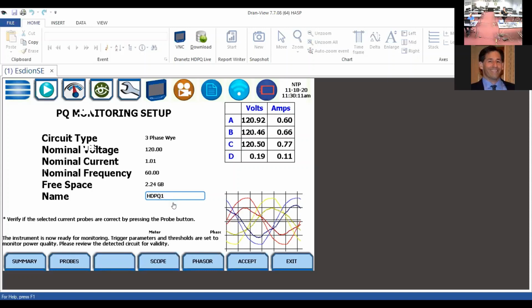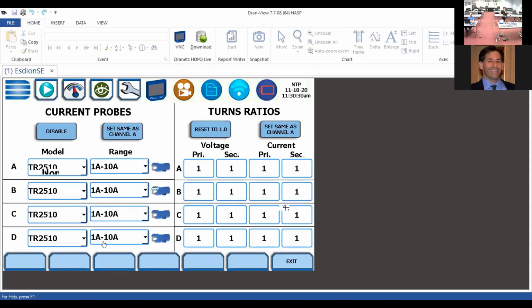The second place in which you would enter information to complete your monitoring setup is the current probes. The instrument wants to know what current probes you are using. By clicking on the probe, or touching if you're local, you're presented with the current probe selection. Now, there are a couple of things to keep in mind here. Number one, the instrument does allow you to mix and match. Some instrumentation out there requires the same current probe on all the channels. This instrument will allow you to mix and match probes, which makes it extremely versatile for a lot of different monitoring applications. But in this scenario, we're going to go to the drop down.